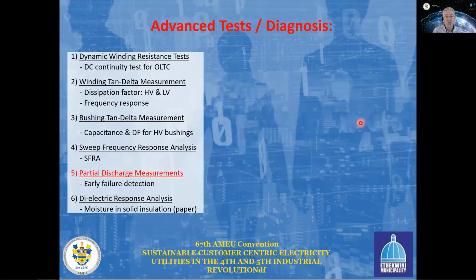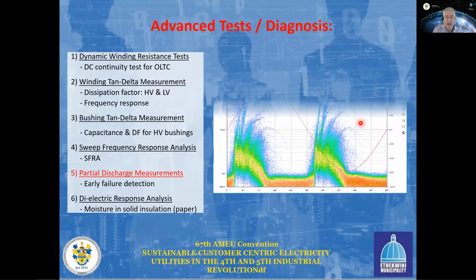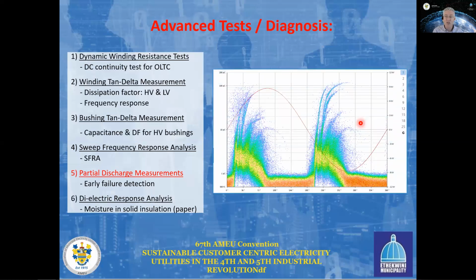We then also have partial discharge measurements. And as the name of partial discharge measurement says, this is partial discharges. Inside our insulation medium, meaning the paper and the oil, there are always certain impurities, which cause little flashes inside those impurities. They can be measured and plotted in a diagram like the phase resolved partial discharge patterns, as you can see here, in relation to the 50 Hertz test voltage applied. And each of these little dots that you see here is a little discharge that happens inside our transformer.